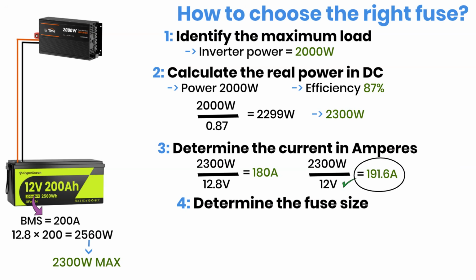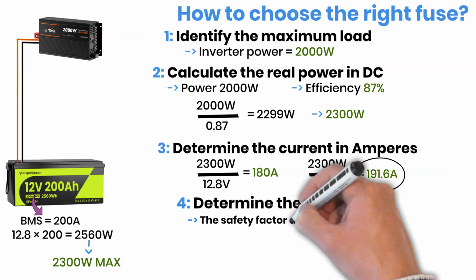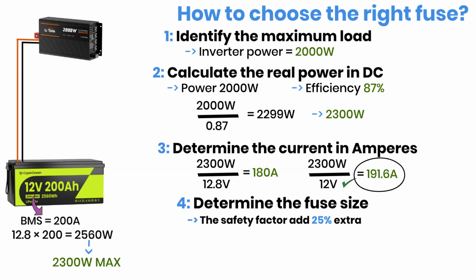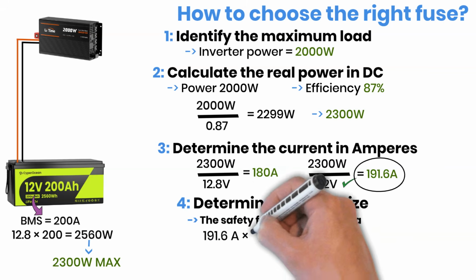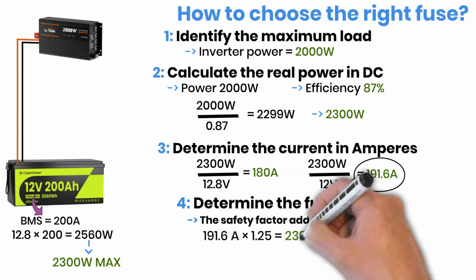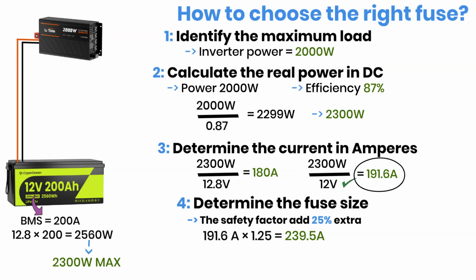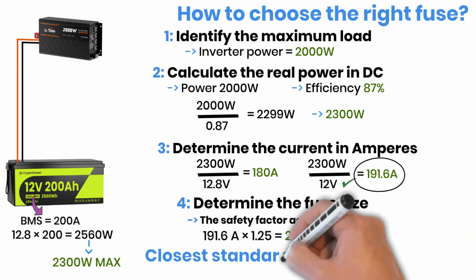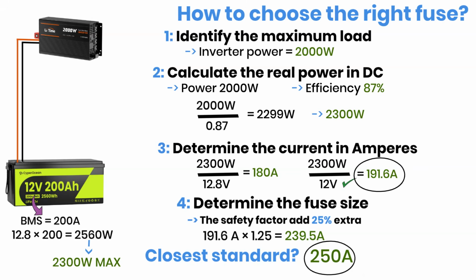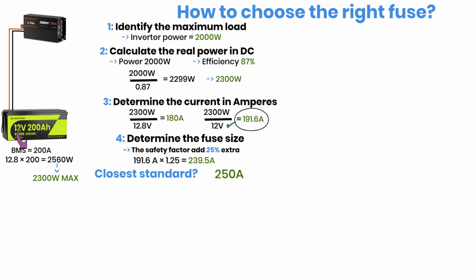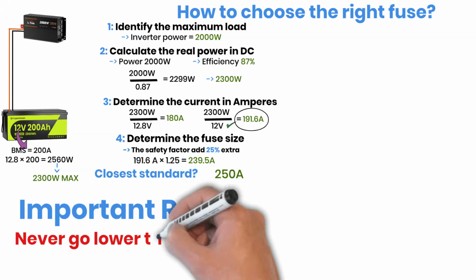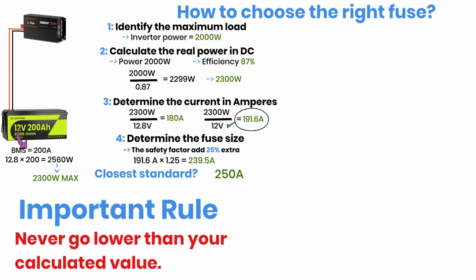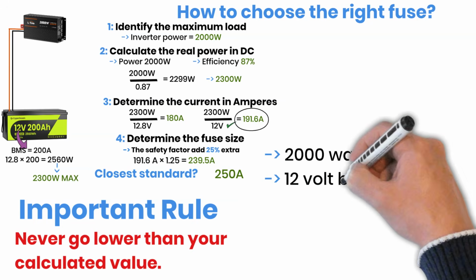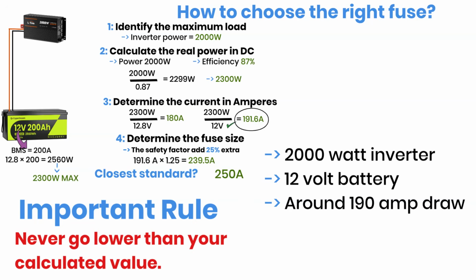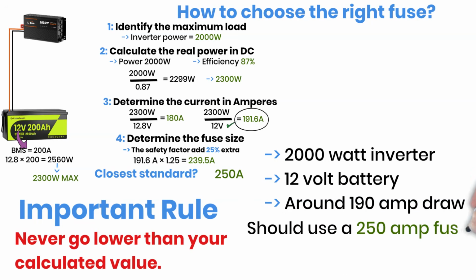We don't pick the exact current value. We add a safety margin so the fuse doesn't blow during normal use. Standard practice is 25% extra. So, 191 amps times 1.25 equals about 240 amps. Now, fuse sizes come in standard values, so we round up to the next available size. That gives us a 250 amp fuse. Important rule: always round up. Never go lower than your calculated value. So for this setup, a 2,000-watt inverter, 12-volt battery, around 190 amp draw, you should use a 250 amp fuse.